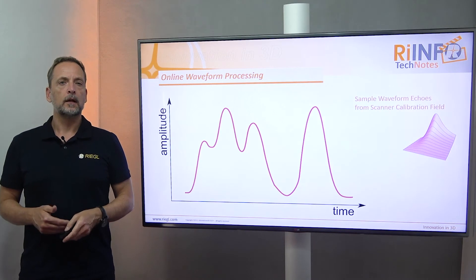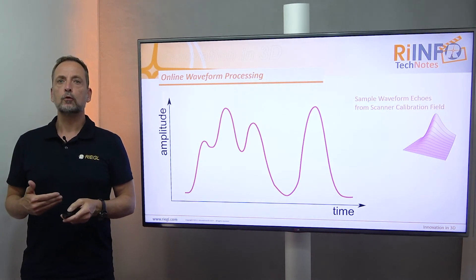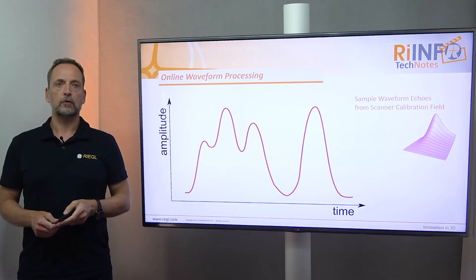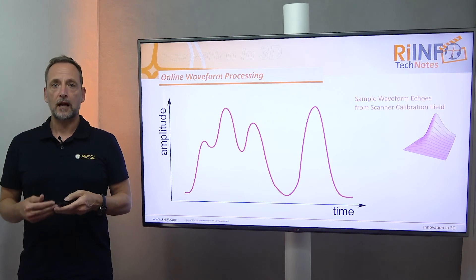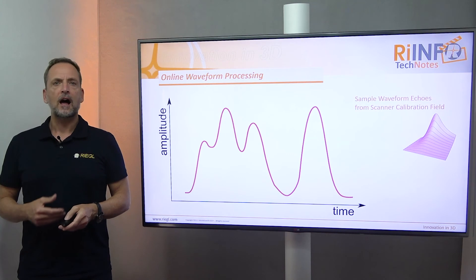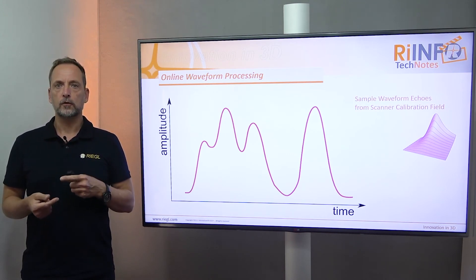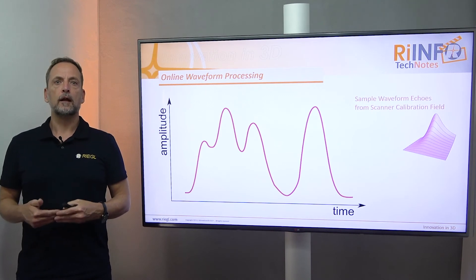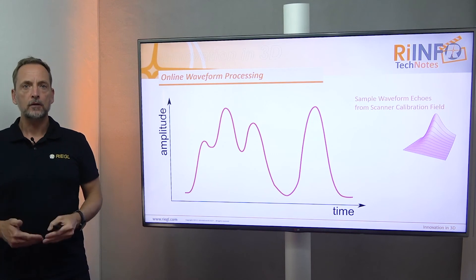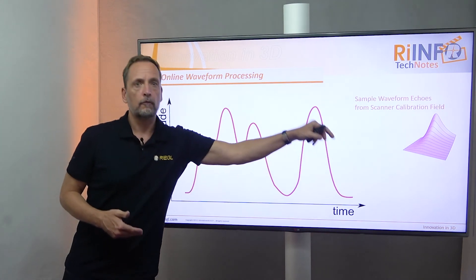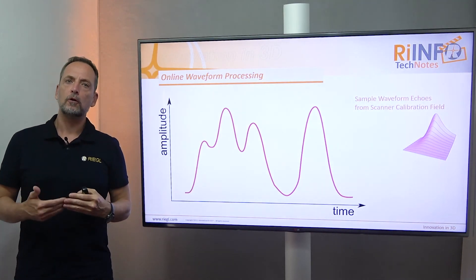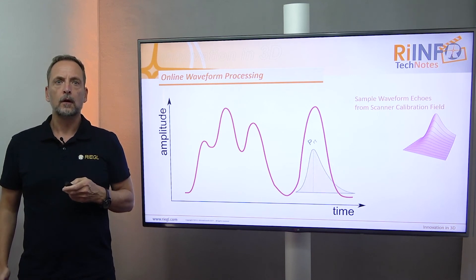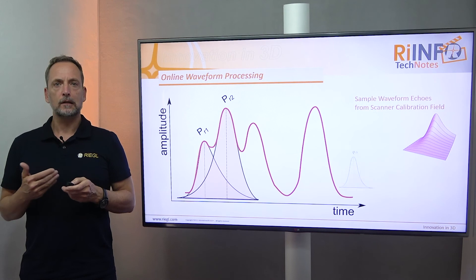Online waveform processing is a completely different approach. As the name already implies, it is working in real time online. There is no need for permanent saving of the digital data stream. Each and every RIEGL LiDAR system is calibrated on our calibration field. There are hundreds of targets of different materials and different surfaces at different ranges with different reflectance values. All resulting echo signal waveforms are collected and combined by interpolating between the most similar waveforms, which resides in a surface of possible waveforms. This waveform surface is like the fingerprint of the scanner — for each and every scanner, it looks slightly different.